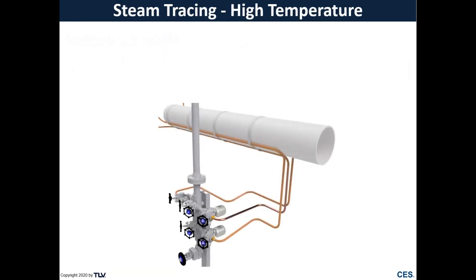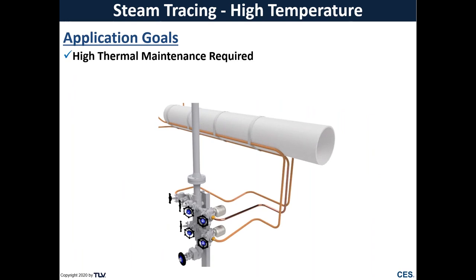Now we also have high temperature steam tracing. So the goal here is that we have a high need for thermal maintenance of that product. This may be a very viscous product that we're trying to keep warm to make sure that everything flows properly. So we want to make sure that we're getting as much heat into that product as possible with these tracing lines. So we want a steam trap with no backup.